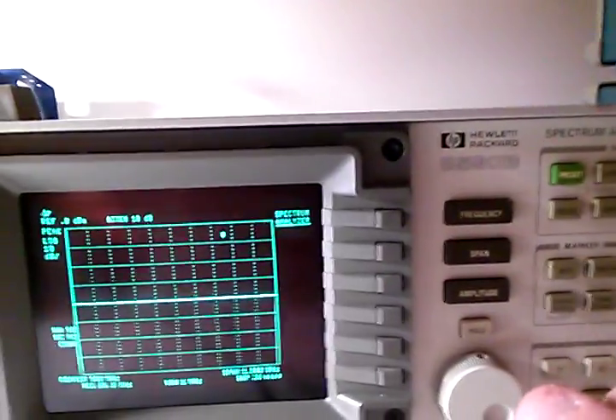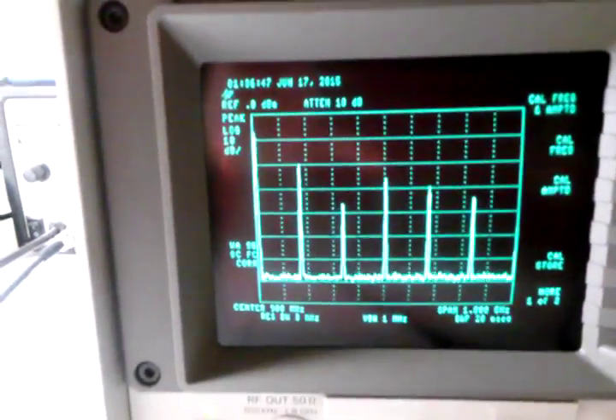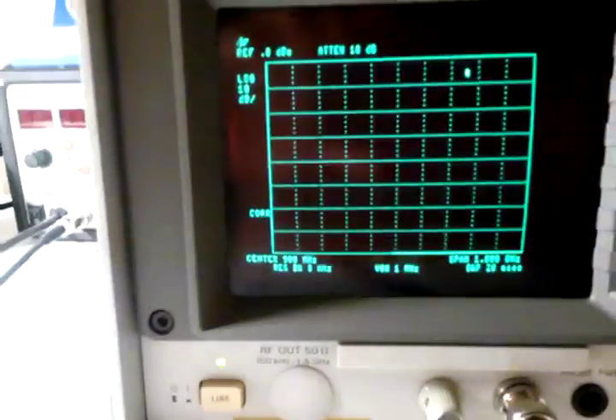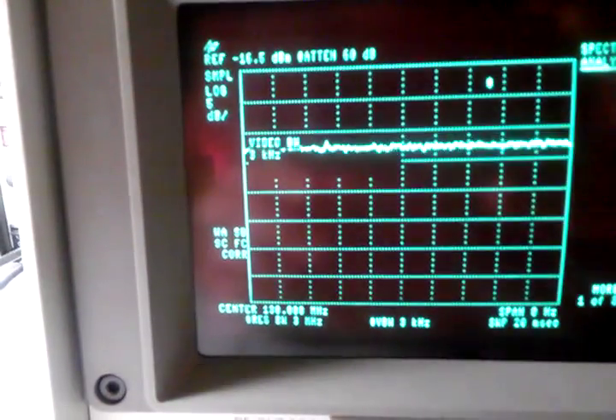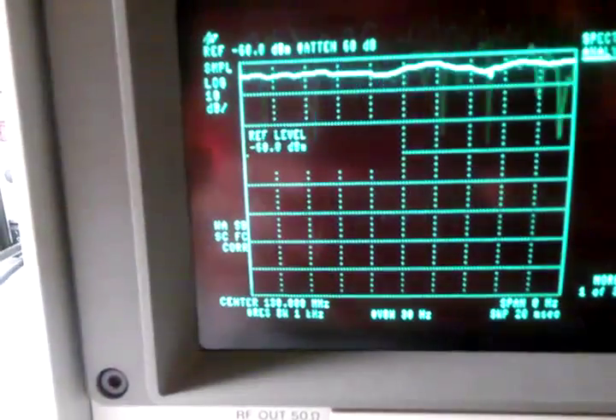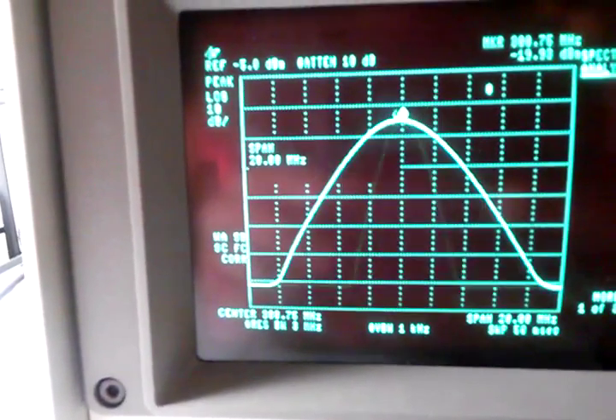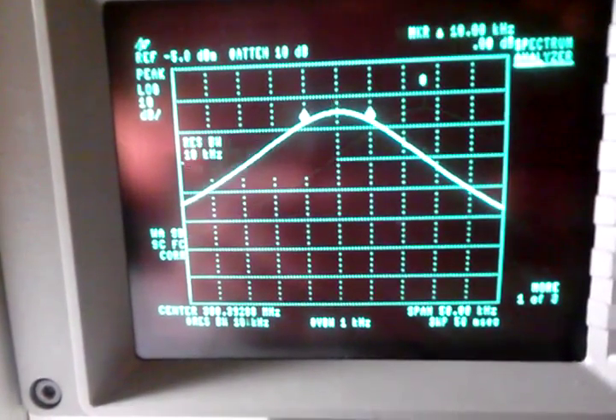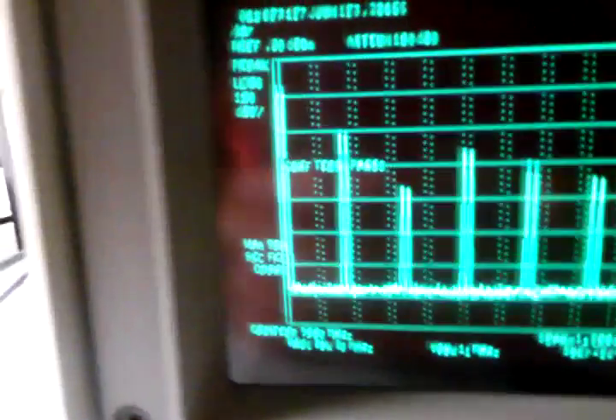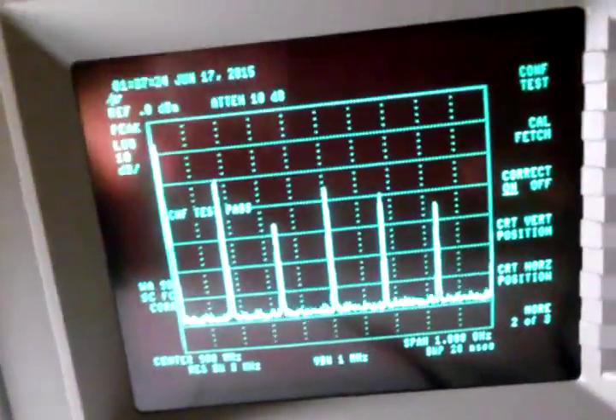We're going to go back to preset, back to the harmonics. And now we will run confidence tests. Confidence tests pass. And it wasn't passing that at all before.